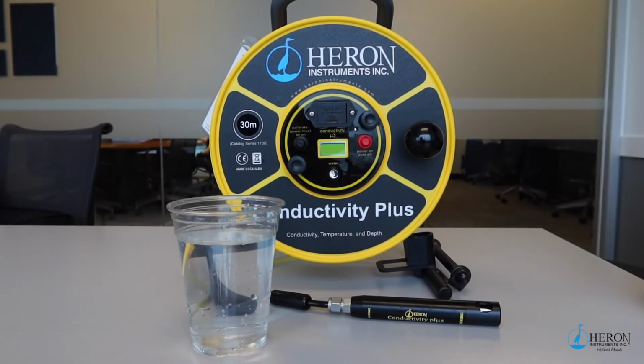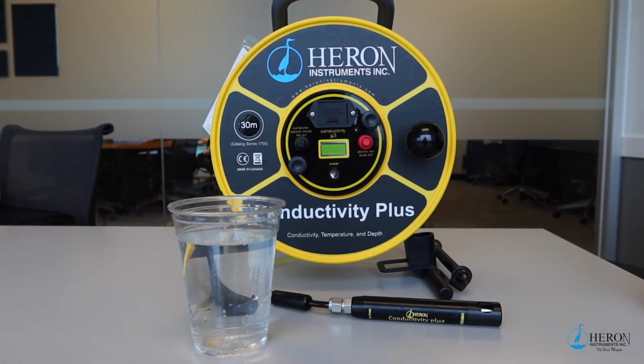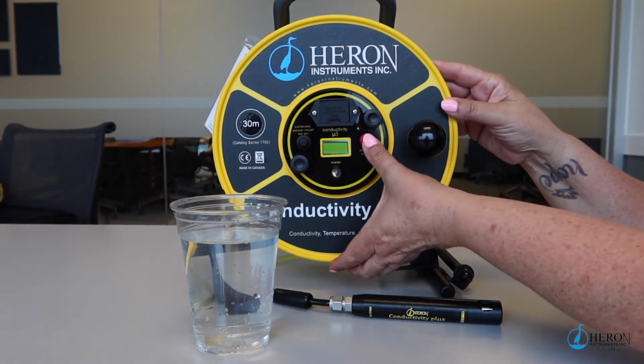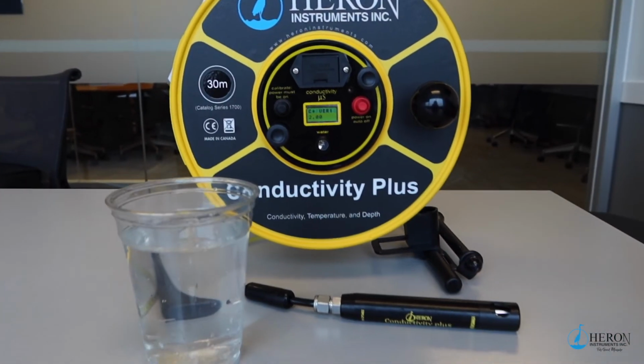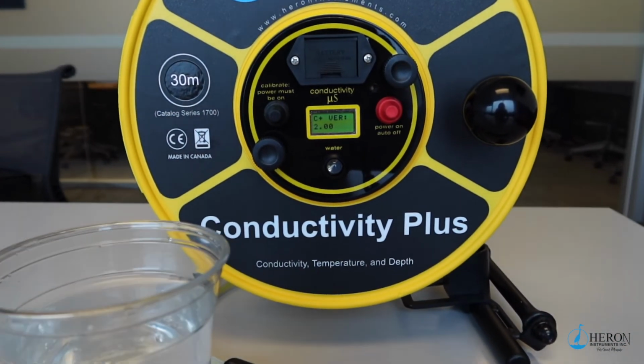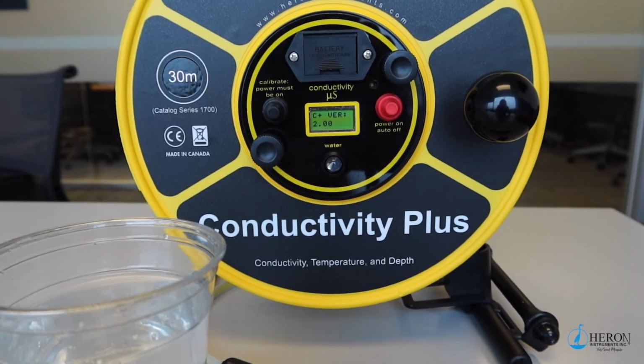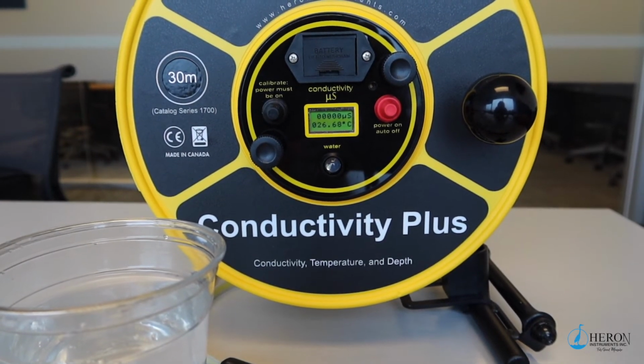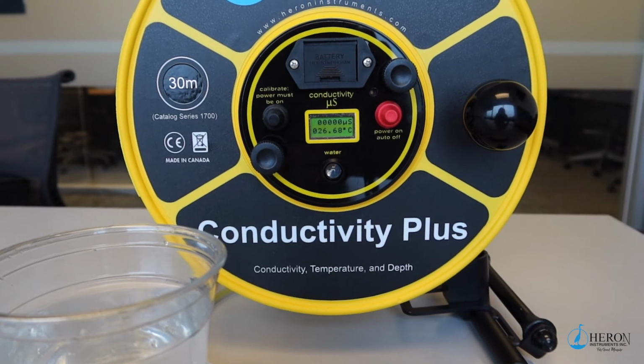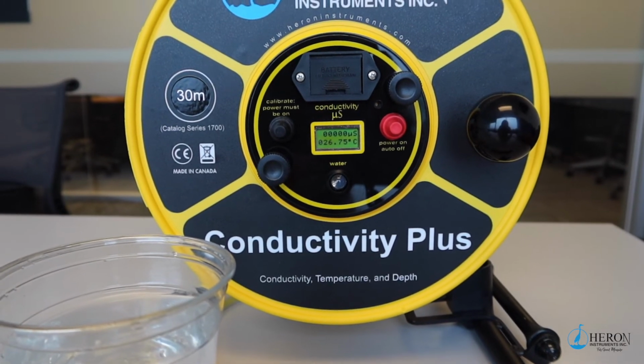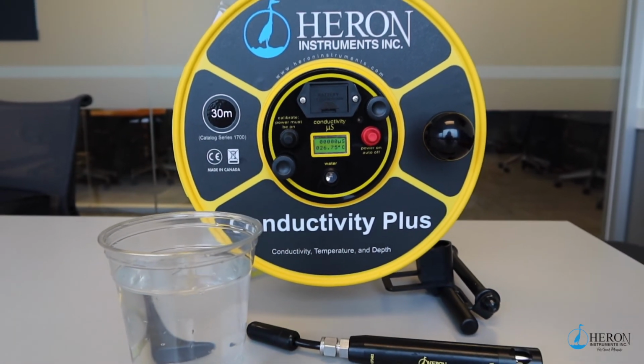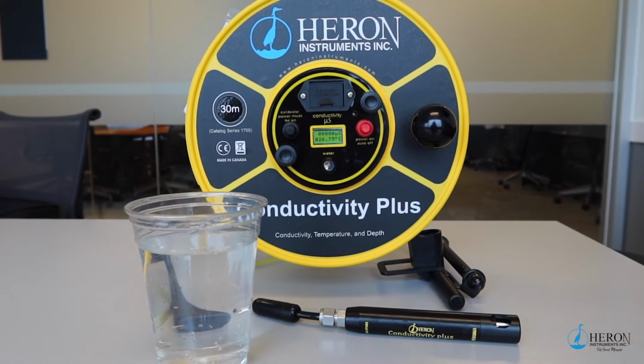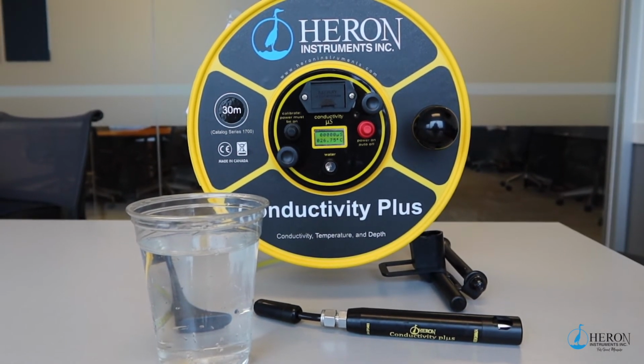Before going out in the field, you should always test your unit. First, test the battery by pressing and releasing the red power button. A brief message will appear indicating firmware version. The digital display will then update with the conductivity and temperature readings. If the unit does not turn on, replace the 9-volt battery. The probe will synchronize with the display panel after 4 seconds.